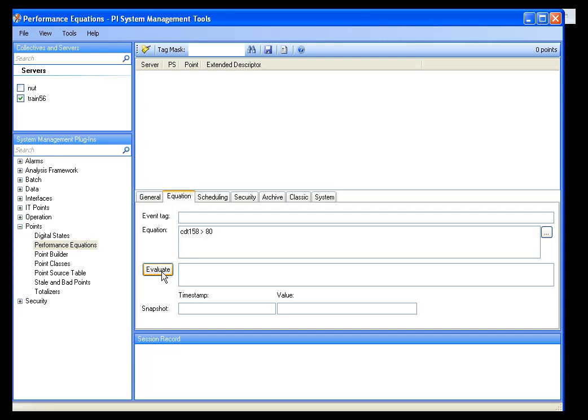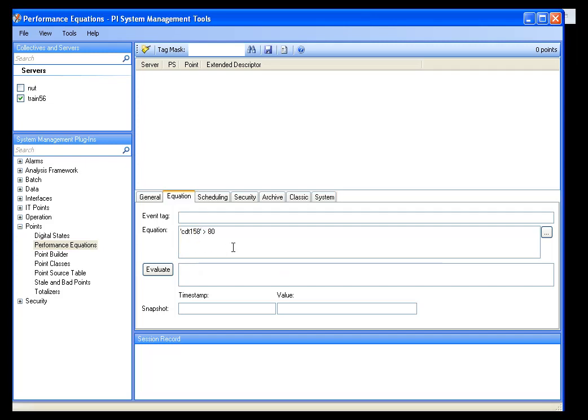If I hit the Evaluate button, I'm going to get an error because I need to pay attention to the specific performance equation syntaxes. A quick rule to remember: tag names and timestamps go in single quotes, strings in double quotes. You can see here that I clearly have a tag name, so I can put single quotes around it, click Evaluate, and you can see that this does evaluate to true.